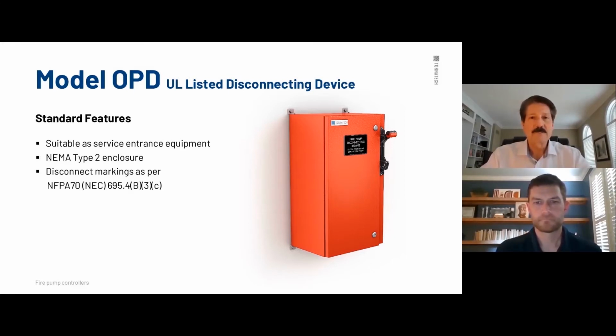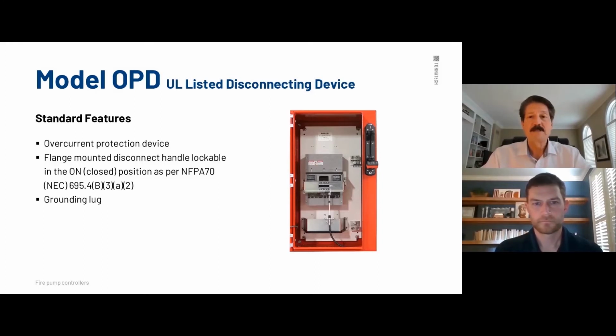It is NEMA 2 encased, exactly what a fire pump controller is too. NEMA 2 enclosure, which is like a drip proof. It's just light falling water. And again, the disconnect markings are per code here shown. It's got a flange mounted operator, a lockable door, and you can see the compactness of this already as compared to what a fusible switch, if you've encountered using a fusible switch, you could imagine the size difference it would be. The inside, very, very streamlined. Again, a case breaker. We have an operator coming off the front of the faceplate itself to operate the toggle.